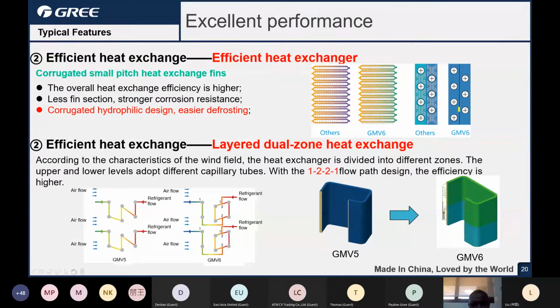And the design structure of the heat exchanger is also changed. For GMV5, that's a total one-piece heat exchanger. For GMV6, we separate the condenser into two independent parts, an upper part and a lower part, and they use two independent capillaries to distribute the refrigerant. So let's have a look here. For the GMV5, there is one inlet and one outlet for the outdoor unit heat exchanger. And for GMV6, there is one inlet, but we separate the distribution to the upper part of the heat exchanger and the lower part to get a better heat exchange with the ventilation.